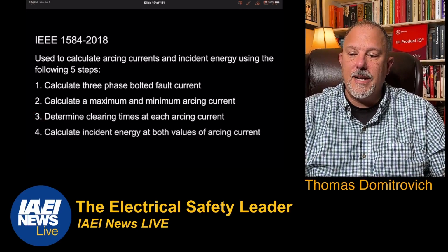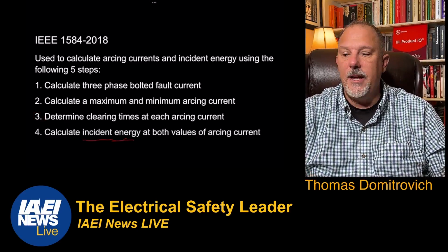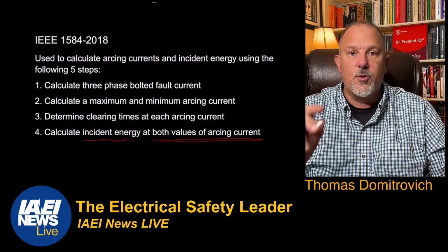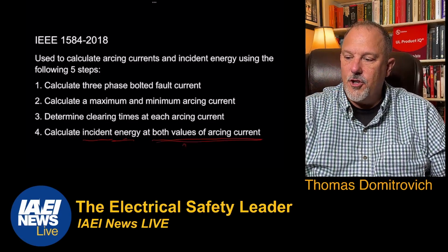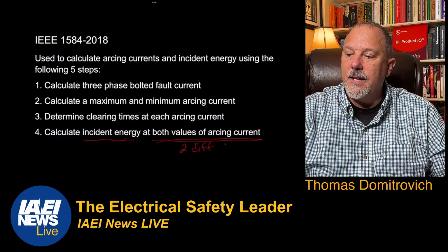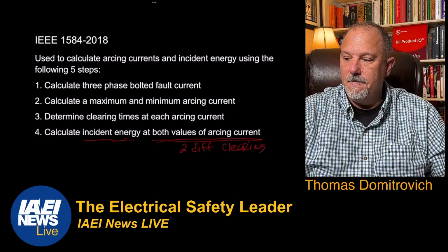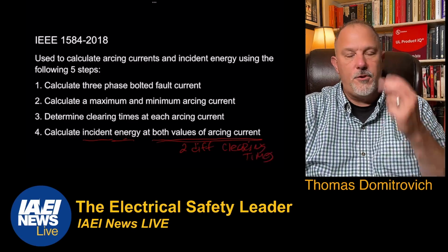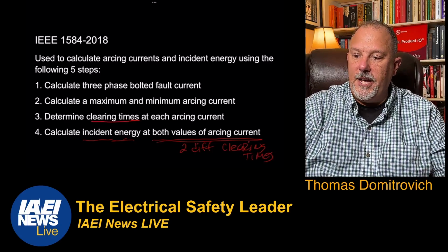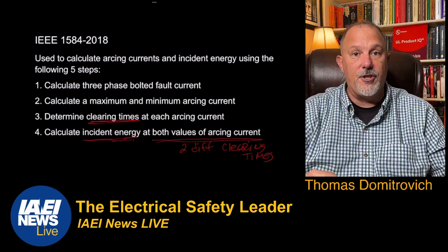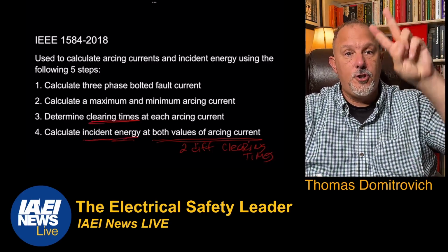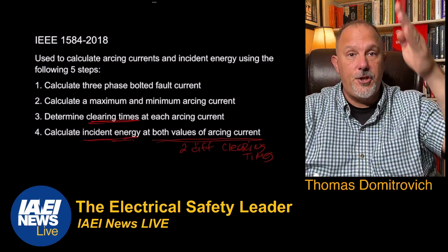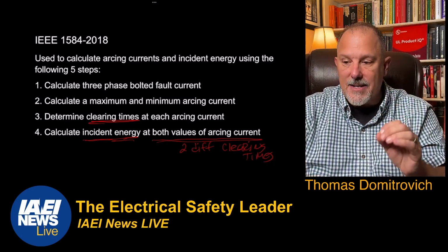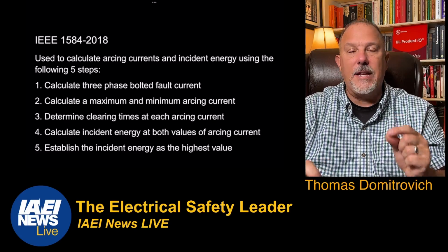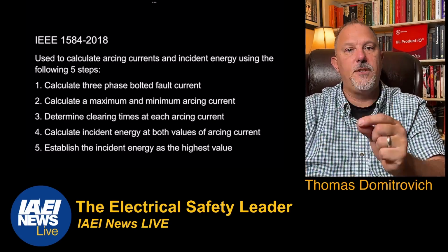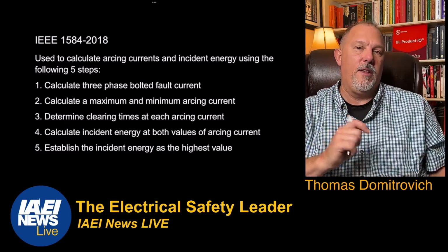And then once you know the clearing times, now you calculate incident energy at both values of arcing current, which will have two different clearing times. So 2 values of arcing current with each clearing time, I calculate incident energy. So I'm going to have 2 arcing currents, 2 corresponding clearing times, and 2 values of incident energy. The maximum energy that is a result of both of those calculations is what I would label my equipment with.